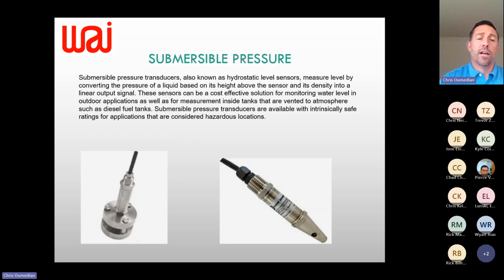Submersible pressure — so yes, it's pressure-based, but it's used for tank level. These come in a couple of different styles, similar to the pressure transducers we started with today. However, there's a weight, called a bullet, that sinks it to the bottom of the tank. The media enters through a small hole, and just like before, a diaphragm flexes a strain gauge based on how much pressure is there.